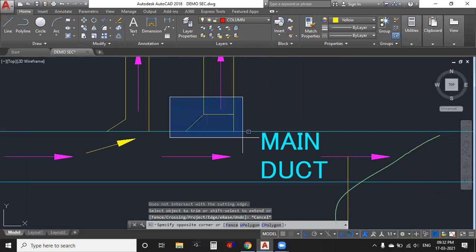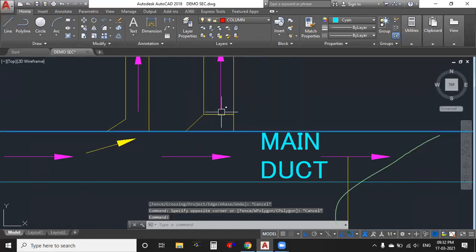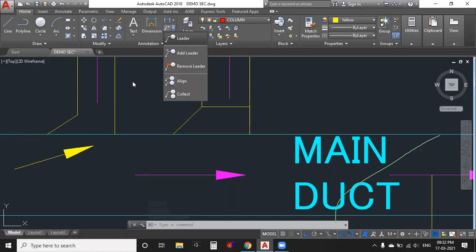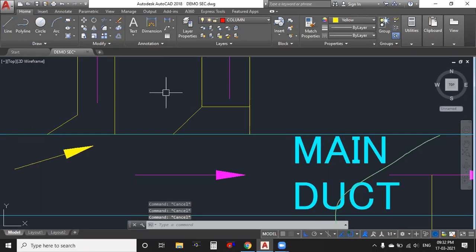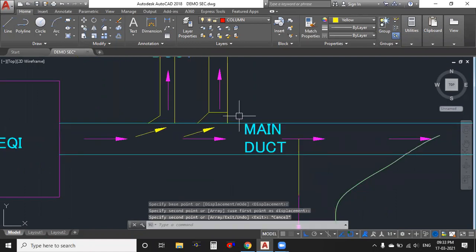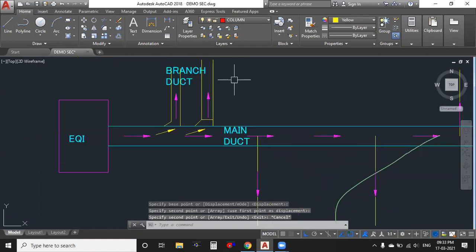This is your shoe neck. Preparation of shoe neck: from the main duct, take a 150 mm half set. After here again 150 mm, you are going to maintain a 45-degree angle. To maintain the 45-degree angle, we make the shoe neck. Clear? If you are maintaining a shoe neck, what will happen? Your air will pass easily from the main duct to the branch duct.